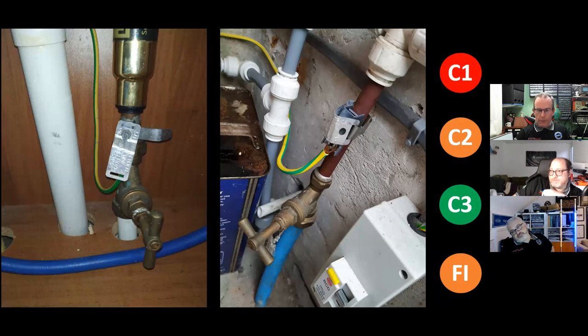And then the one on the left, that's a white plastic pipe coming in. And then the thing above it is one of these things that claims to stop limescale. It is a metal-bodied item, but if you look at the bottom of it, it's got a black plastic push fit connection. So again, what are we actually bonding to? One thing's present, but does it need to be present? And if it does need to be present, is this really the right place to be connecting it?